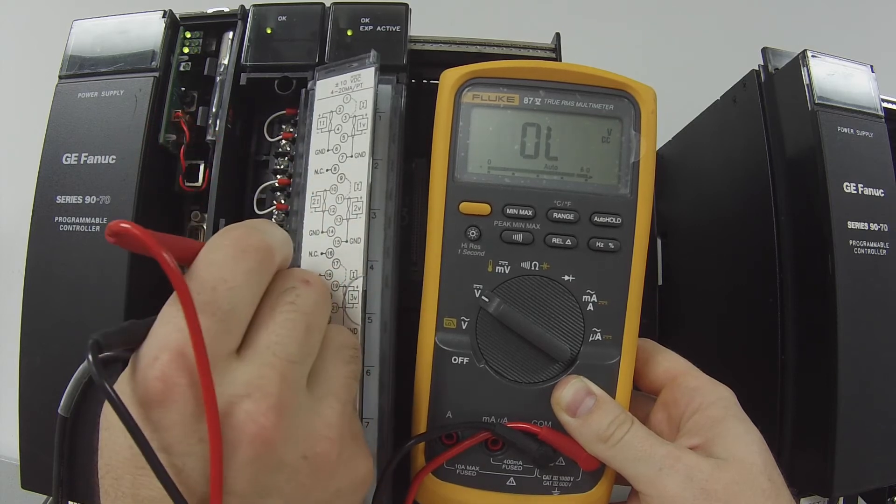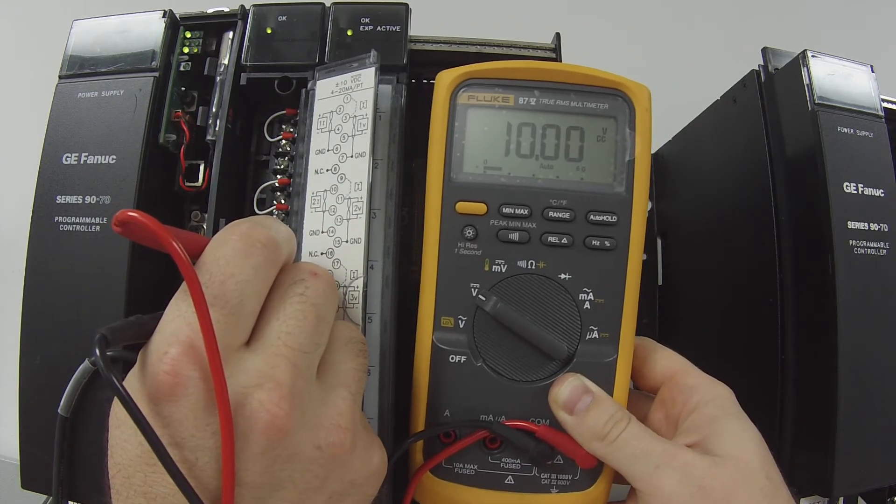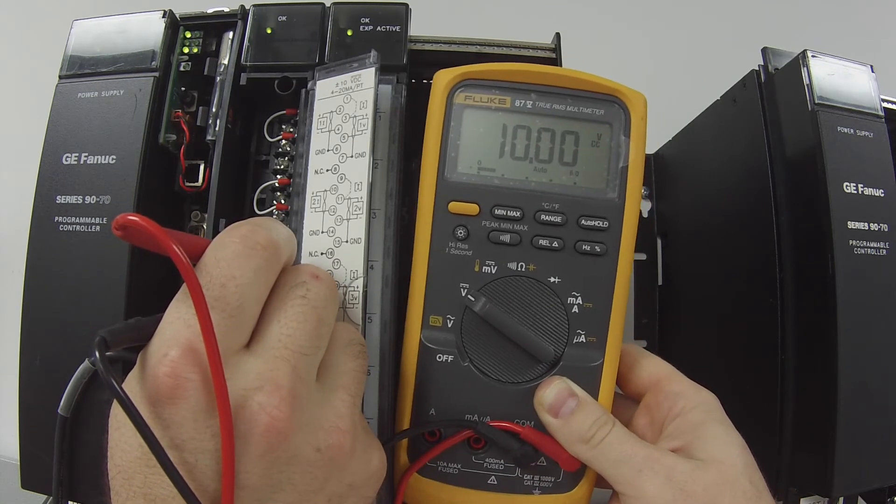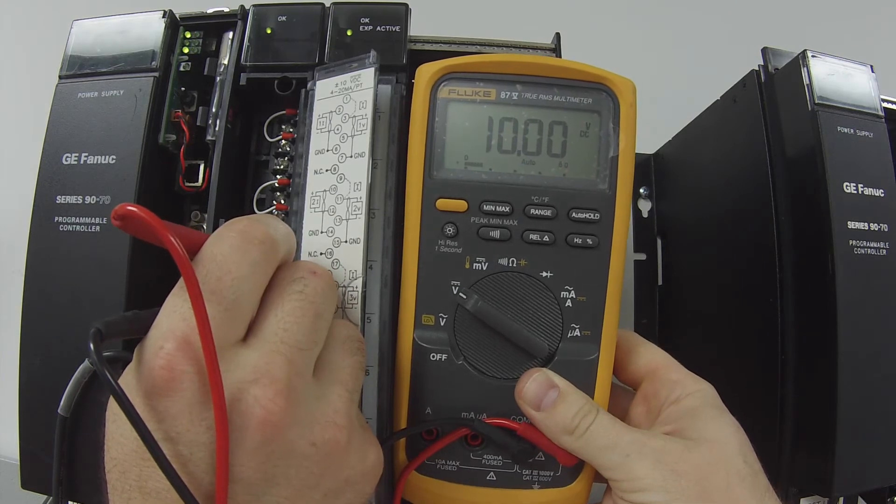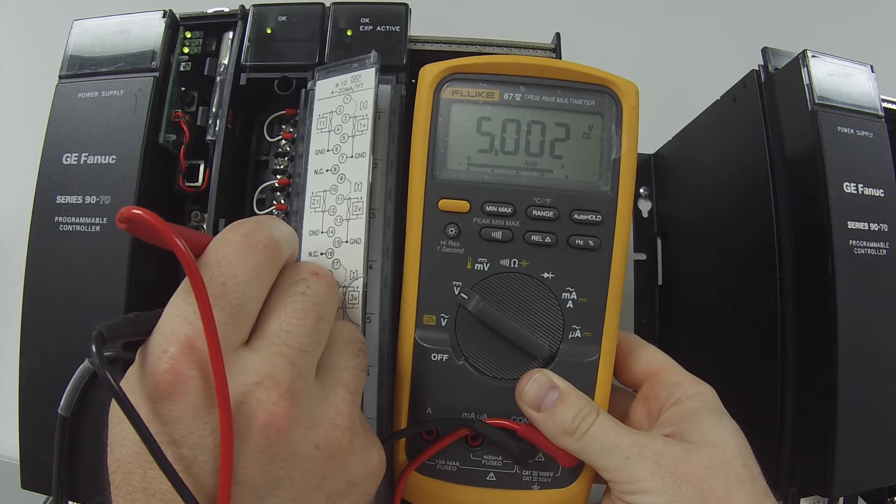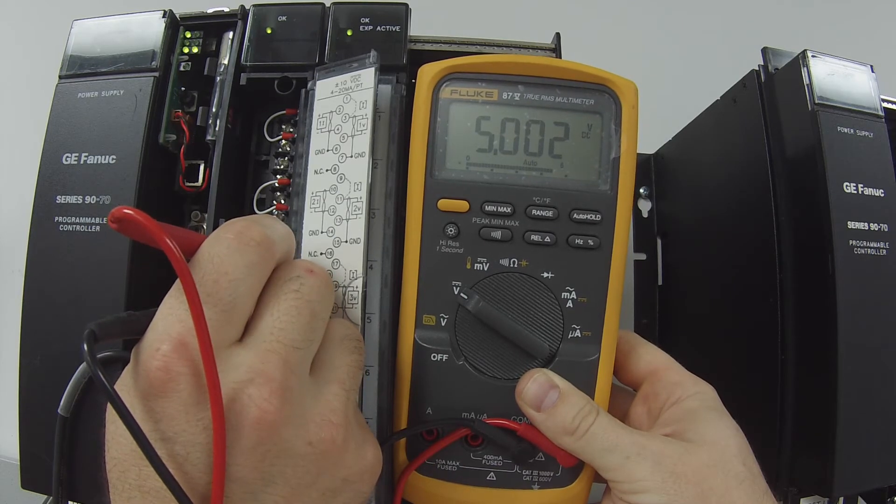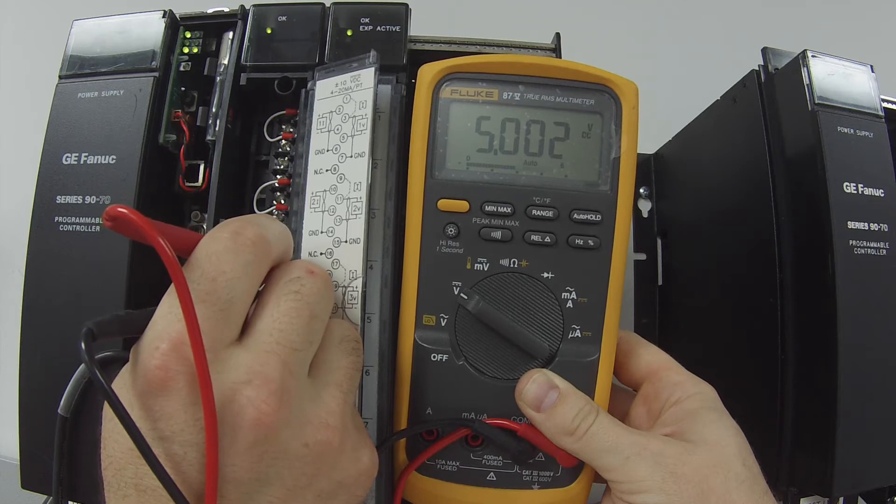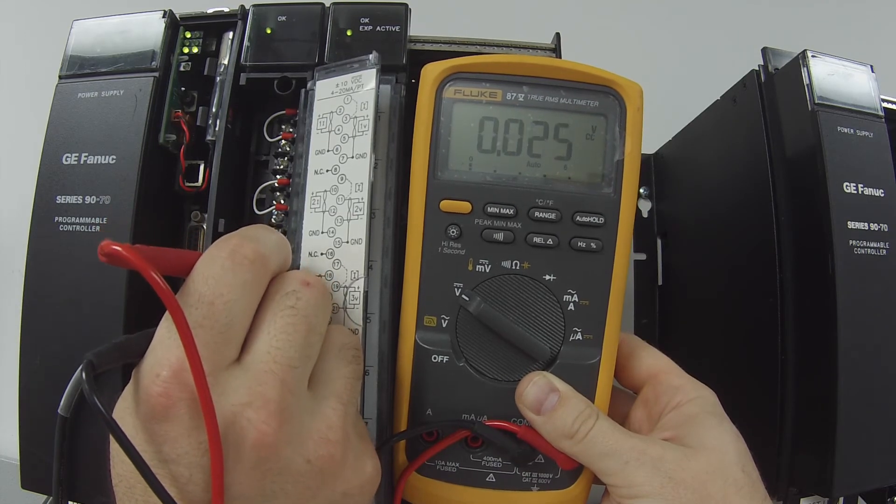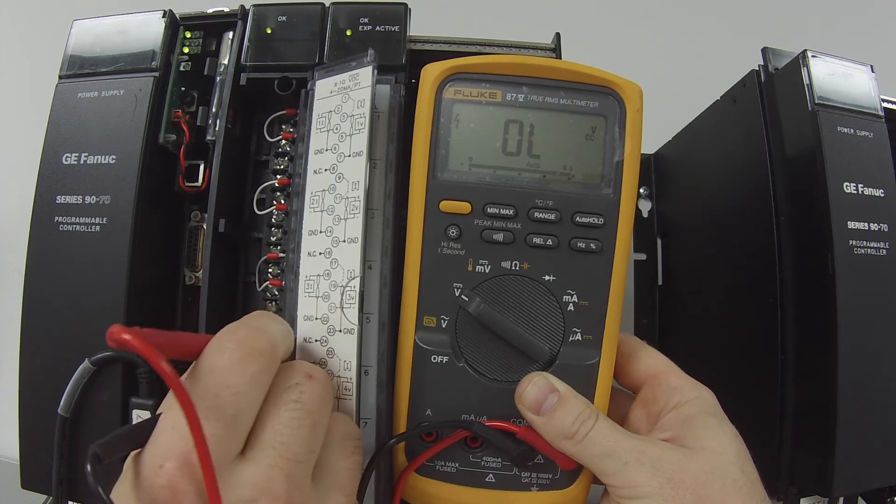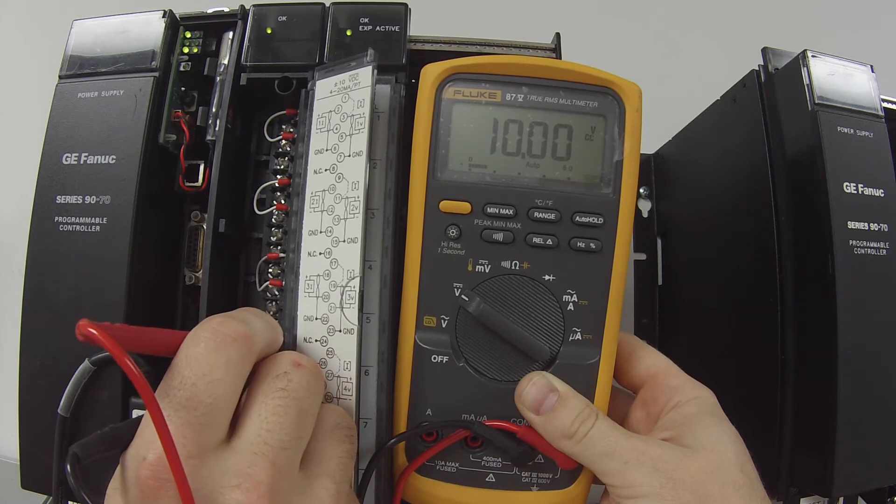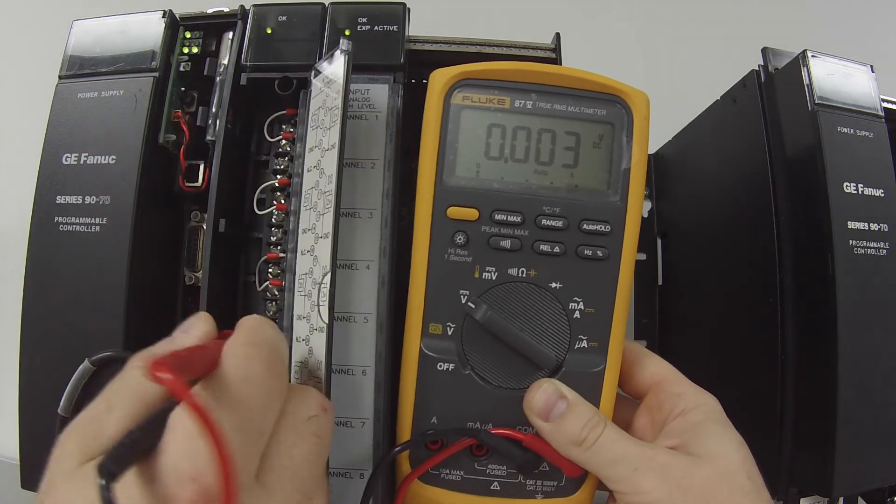Now here I'm going to do something a little different. I have a value of 32,000 so I'll cut that in half to 16,000 and I should get half the reading, 5 volts. And I'll cut that in half, 8,000, I'll get half that reading which would be 2.5. I'll go ahead and zero that out. That's something you could do to all channels. I just put it on that one so we wouldn't have to do that on each one to save some time.